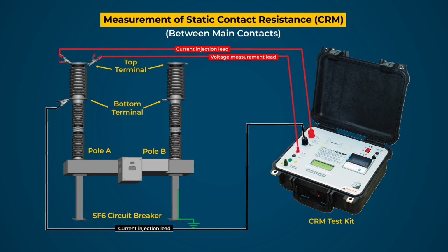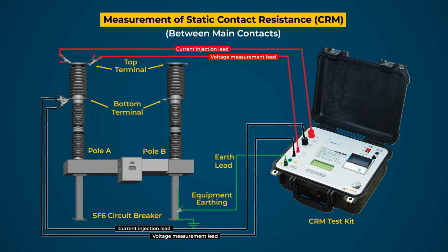Now similarly connect the positive voltage lead of the test kit to the top terminal of breaker pole A and connect the negative voltage lead of the test kit to the bottom terminal of breaker pole A. Also, connect the master earthing terminal of the test kit to the equipment earthing. Check all the connections and the setup is ready to perform the test. Now, press the test button.